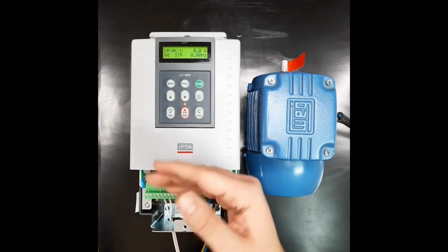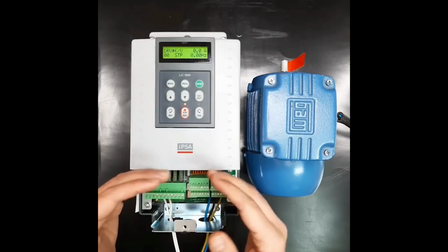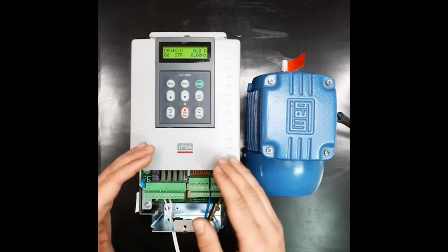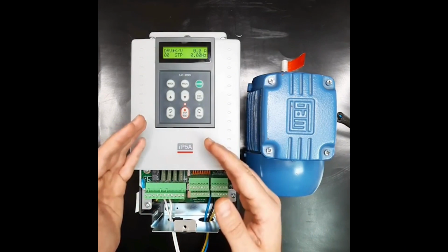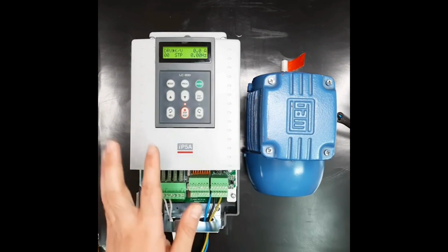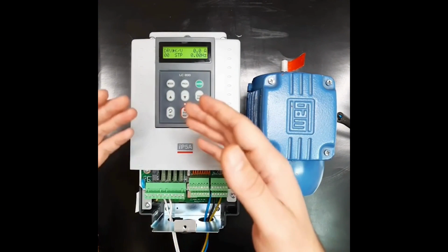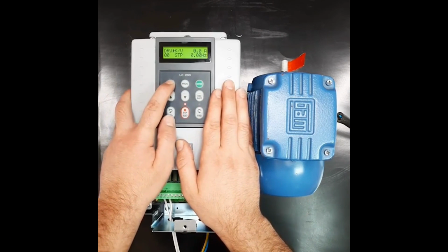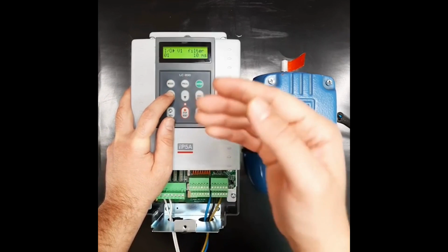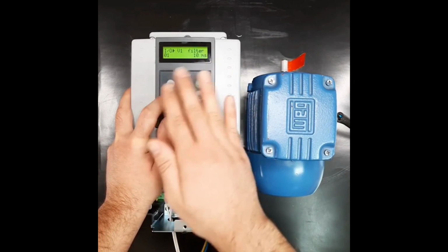To put it simply, we need to specify for the drive what frequency to apply to the motor for a given input signal. For example, for an input signal of 0 to 10 volts, control the motor from 0 to 60 Hz. To set these 4 points on the iP5 drive for the analog voltage input, we need to go into the I/O parameter group and use I.2, I.3, I.4, and I.5 to set these 4 points.